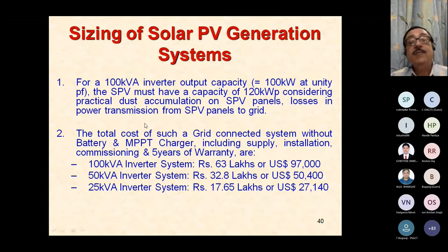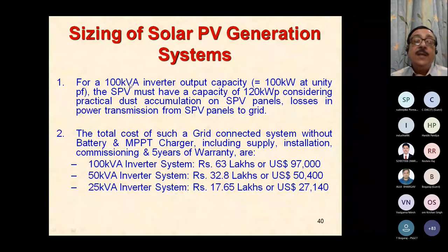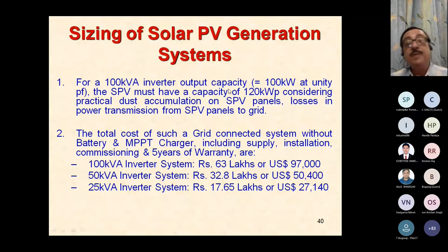If you take a look at the sizing, how do you go ahead with solar photovoltaic generation system sizing? A rough idea, approximate. It's not a mathematically precise calculation that I'm showing. Suppose I want a 100 kVA inverter, whose output shall ideally be 100 kilowatts at unity power factor. In the commercial market there are a lot of tricks. If you have a 100 kVA inverter, some manufacturers say you cannot get 100 kilowatts. I ask why? If it's rated on the current rating, then a 100 kVA inverter should be able to provide me 100 kilowatts of power at unity power factor.